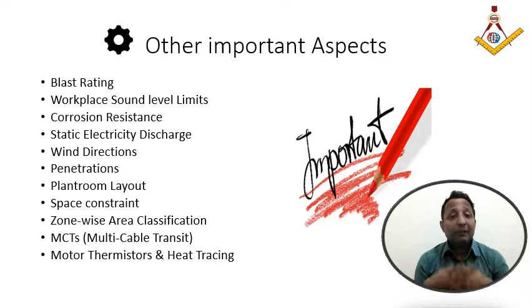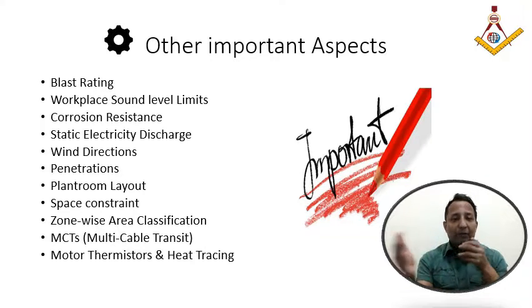Wind direction plays a major role. As you know, being offshore or being in the sea, the wind velocity is very high compared to the land. As you venture inside the sea, you need to check the wind direction, and on ships we cannot control where the inlet and outlet of the fan should be kept. So we normally keep the static pressure a bit higher than required, to cope up with the wind pressure.